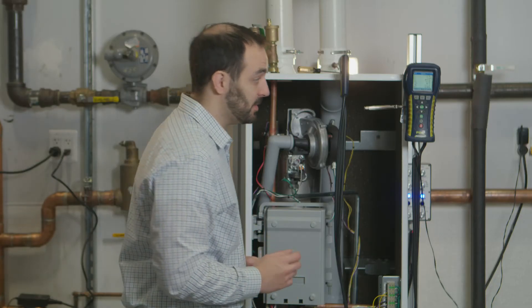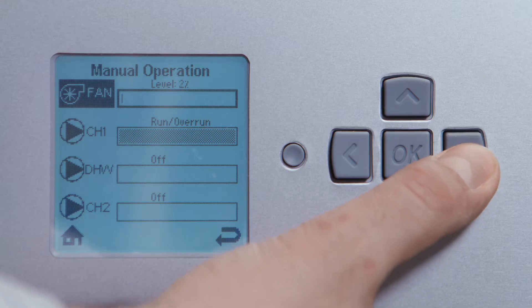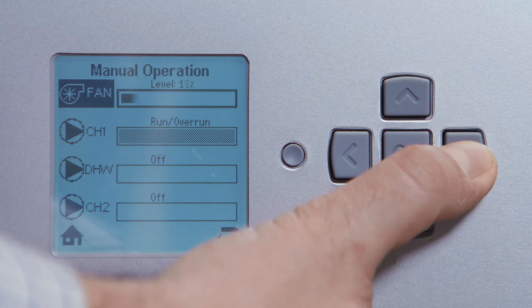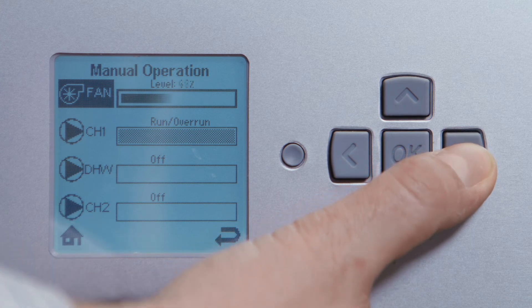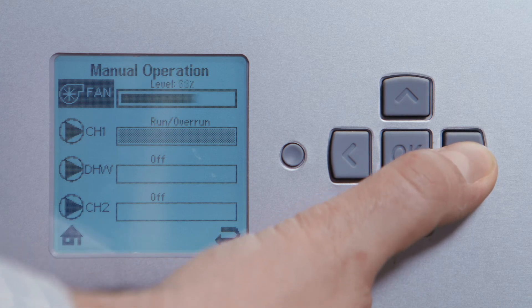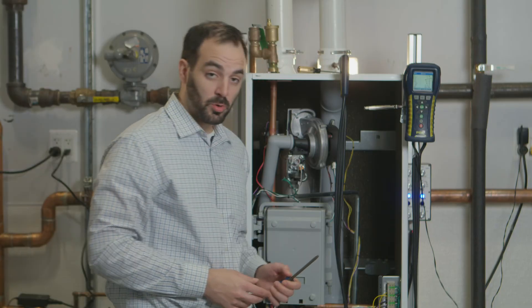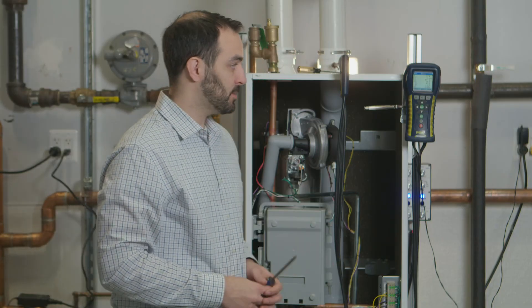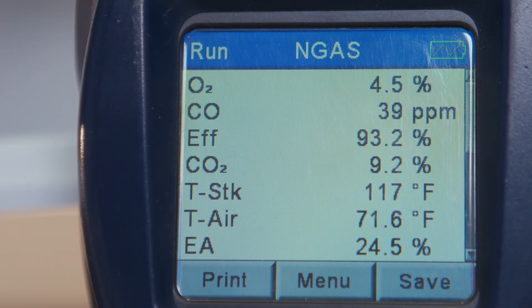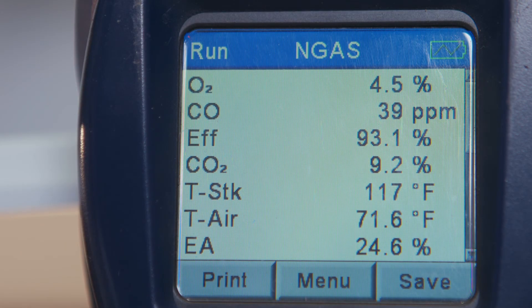Let's go back to high fire and make sure that didn't change. Go back to our panel, press the right button and bring it all the way up to 100%. Give the boiler a second to catch up and the combustion analyzer a minute or so to settle out. Our combustion analyzer has settled right where we left it at 9.2% CO2, which is perfect.